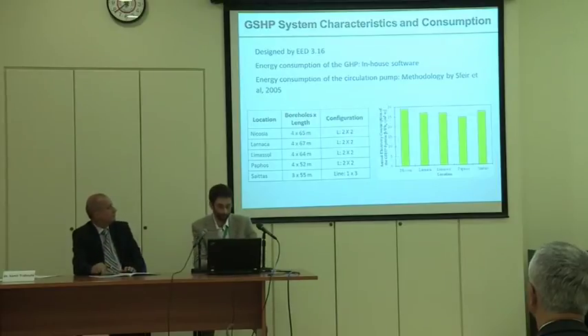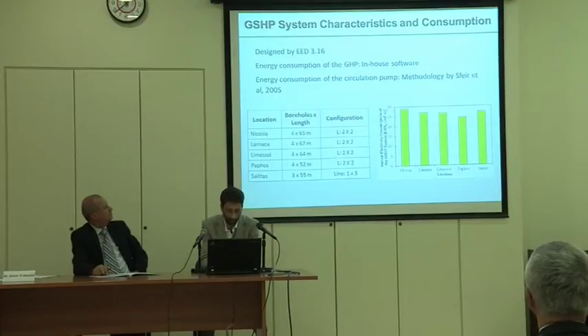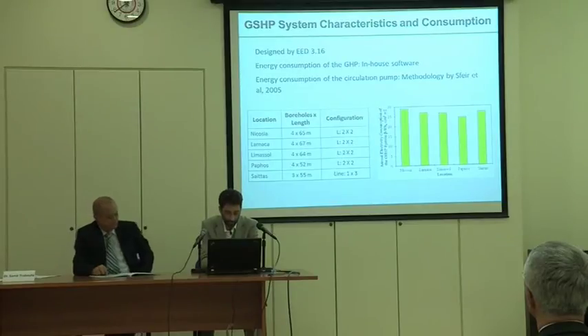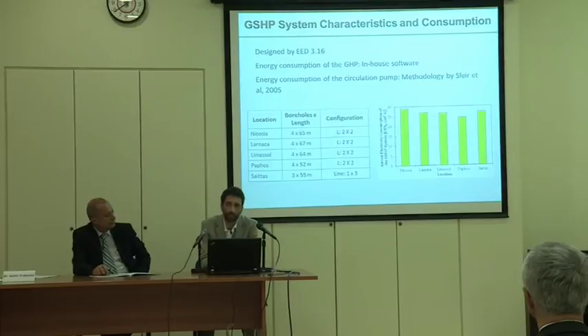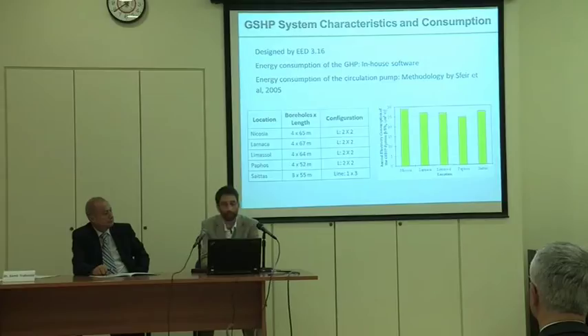The dimensioning of a ground source heat pump system is based on the design heating and cooling load of the building, which has been calculated with the aid of Elite HVAC software. The required ground source heat exchanger length was calculated using the monthly load profile, which has been retrieved from the EnergyPlus analysis, and using the EED design software. Moreover, it was assumed that the ground heat exchanger consists of double U-tube pipelines and was filled with thermally enhanced grout in order to improve the thermal conductivity between the borehole and the surrounding soil. The results of this calculation are presented in this table.